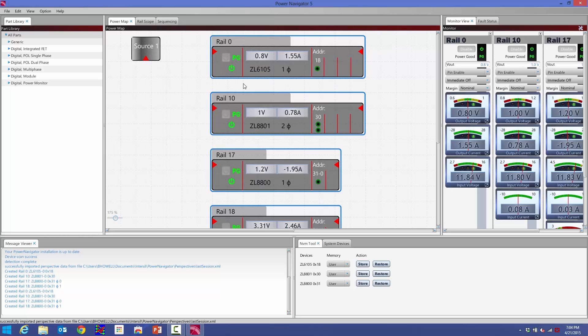The new Power Map tells me what the device is, how many phases there are, what the current output voltage is, what the current load current is. It has a rail name. I can actually change these rail names to make them more descriptive. Over here, it shows me the address that it's at. This one's at a PMBus address of 18.